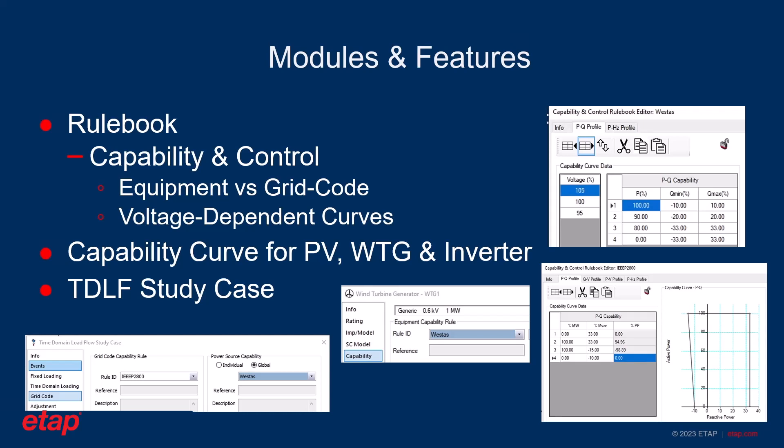Furthermore, the rulebook can be used for element capabilities: the PQ capability of elements can be used from predefined libraries, or the user can add the specific capability of their elements manually based on their vendor data. All these profiles are voltage dependent, so the user can add all the information at any certain voltage level. This includes capability curves for PVs, WTGs, and inverters, and is primarily used for time domain load flow analysis.